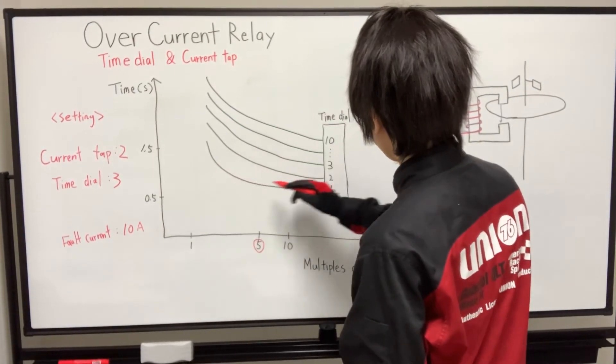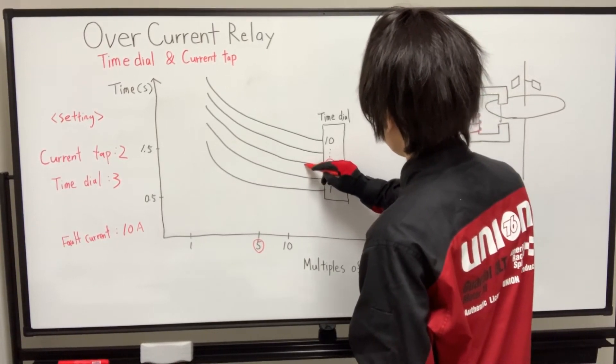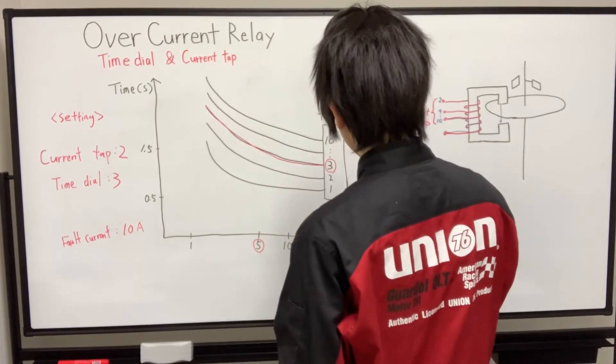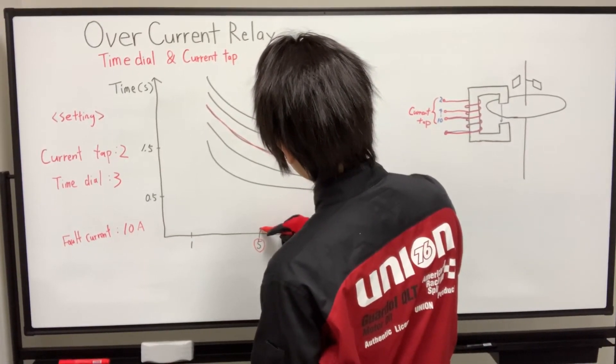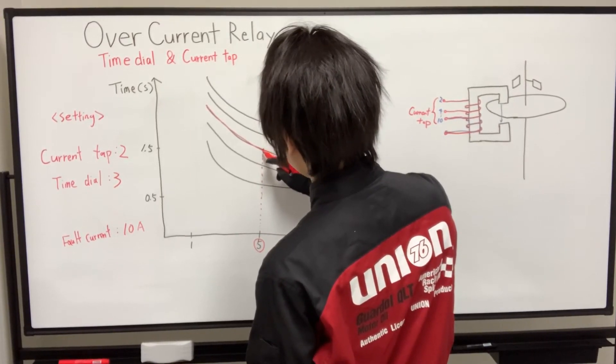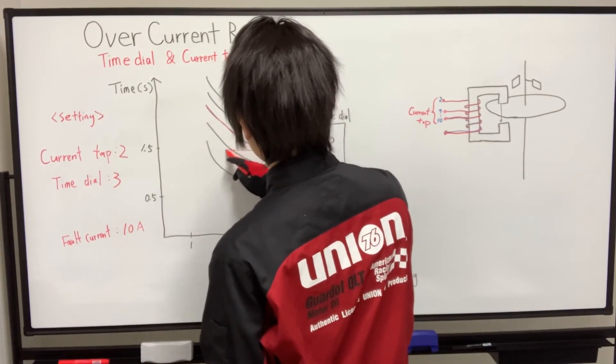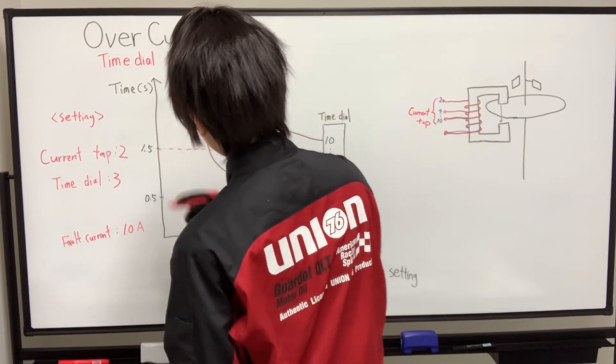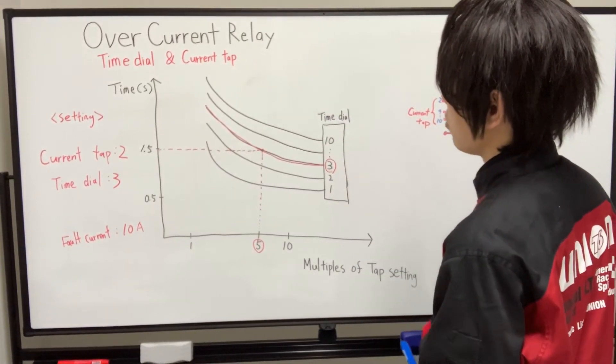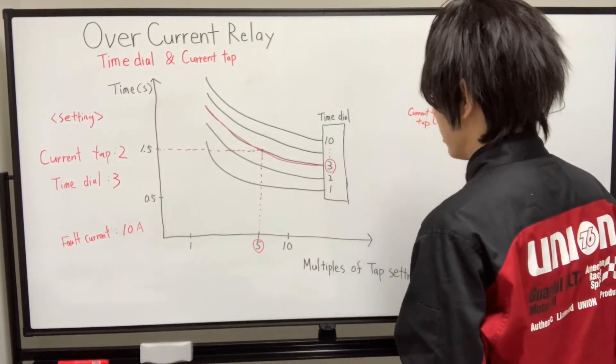And the time dial is number 3, so we need to look at this particular curve. And the 5 is here. So the operating time is 1.5 seconds. So if the overcurrent relay is set to these conditions and the fault current is 10A, the relay operates in 1.5 seconds.